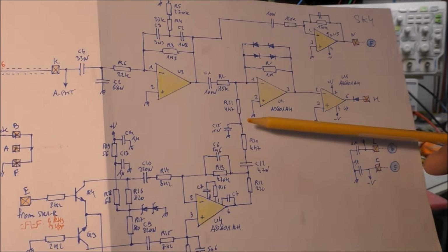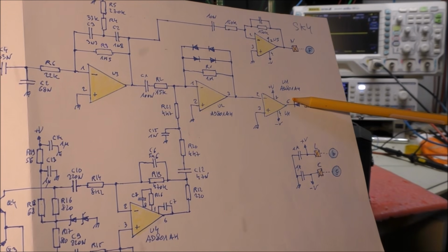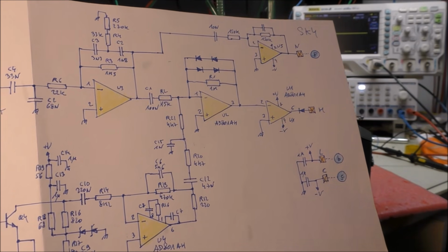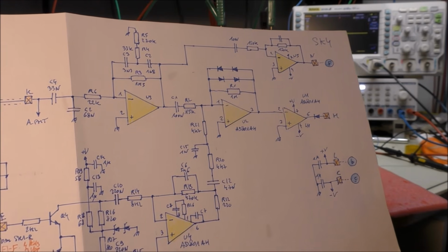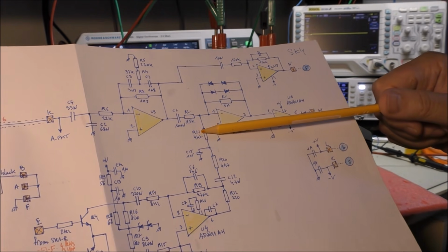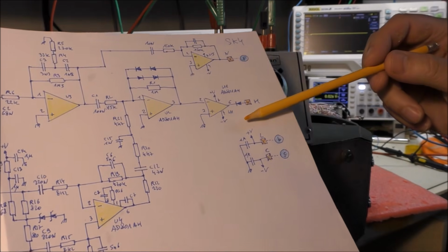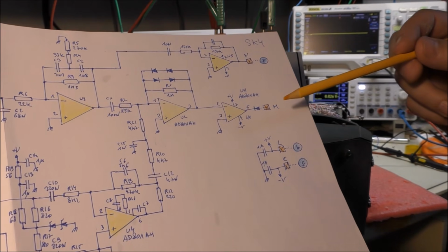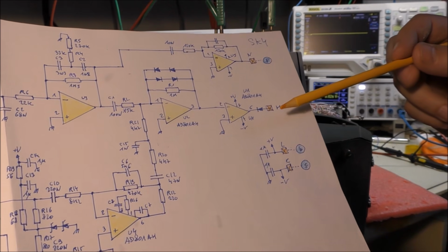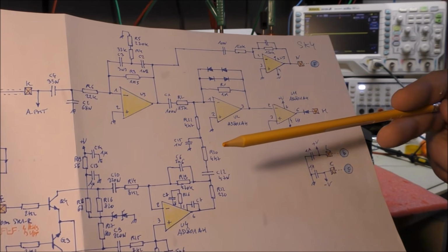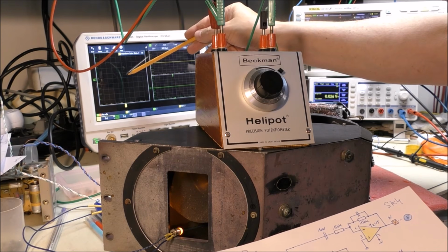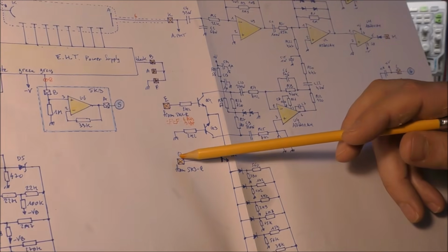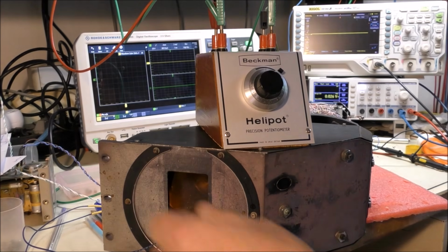When there is no signal here, this circuit works normally. At the output there is a 100 Hz square signal which is fed to the phase detector, and at the output of the phase detectors we have maximum voltages. But if we consider that we have a large 4 kHz amplitude, at the output there will be mainly a square wave at 4 kHz, and in that case, at the output of the phase detector, we will actually have a null voltage. This circuit permits to reduce X and Y voltages in order to change the position of the spot regarding the center. This signal is connected to another circuit which is on another board.